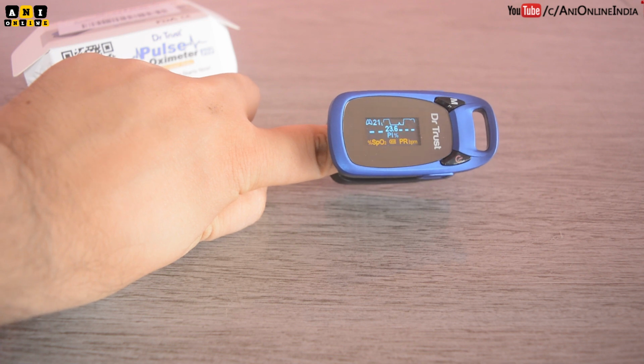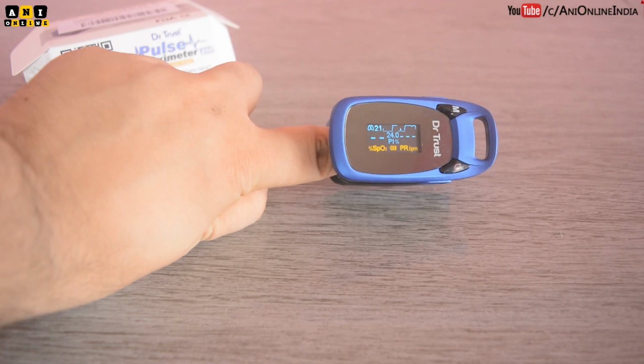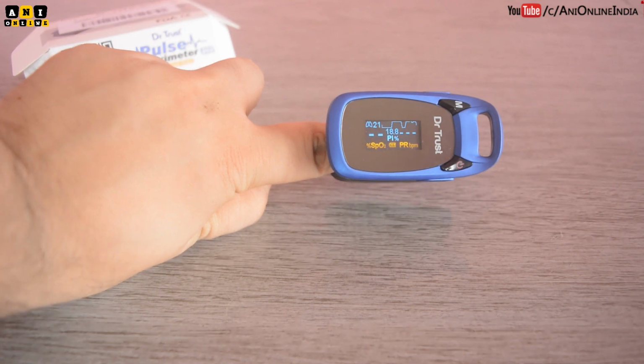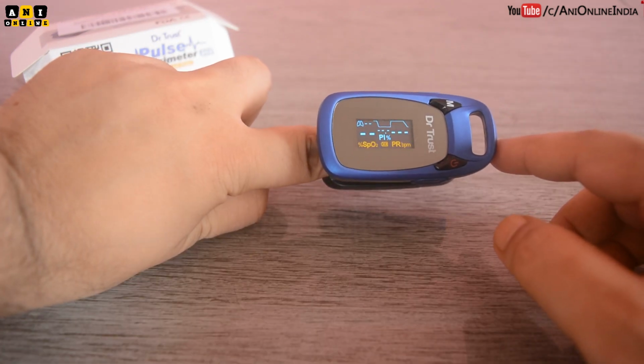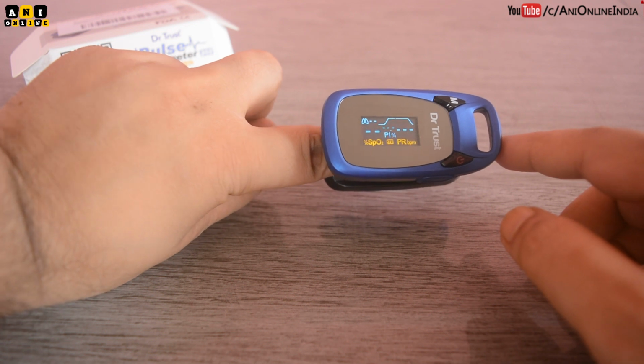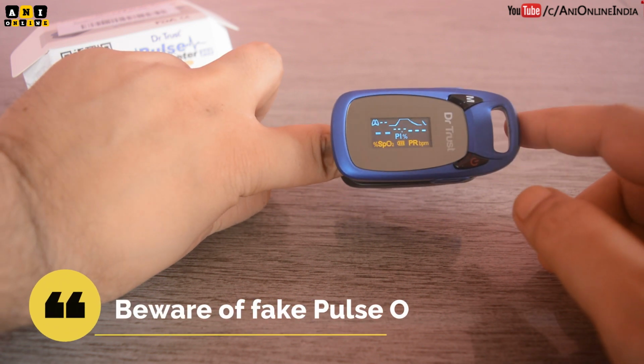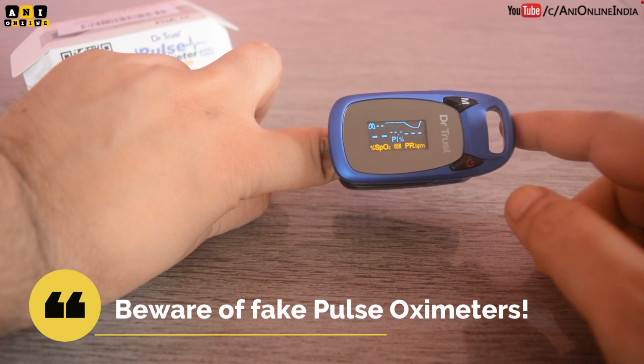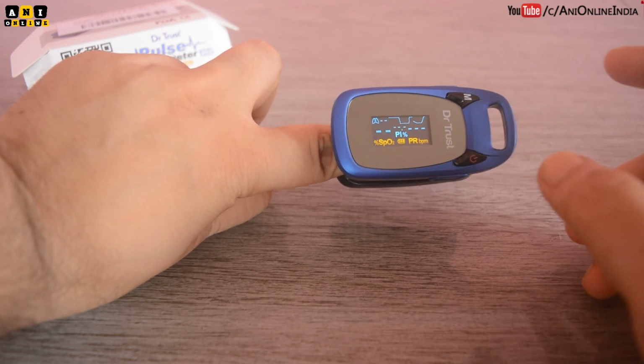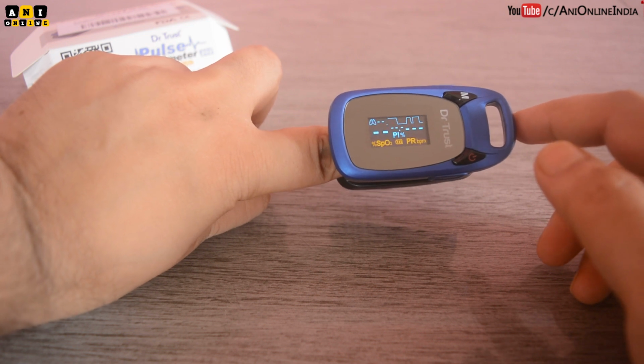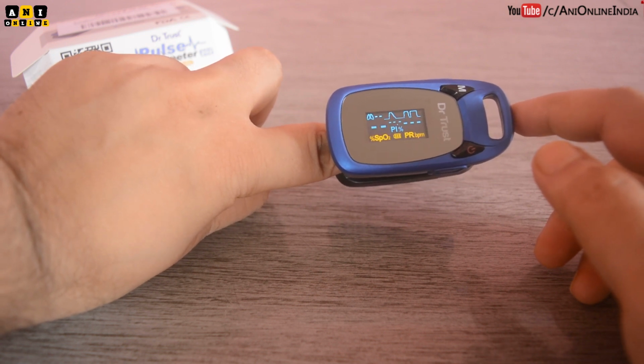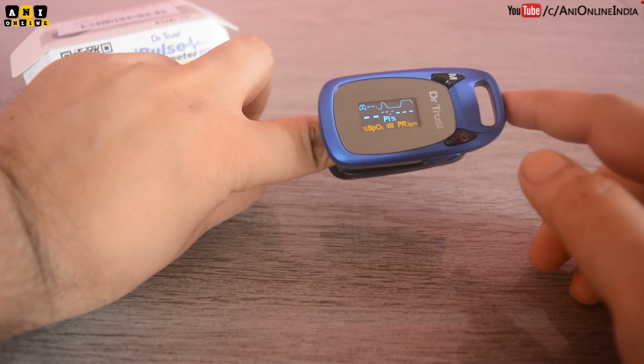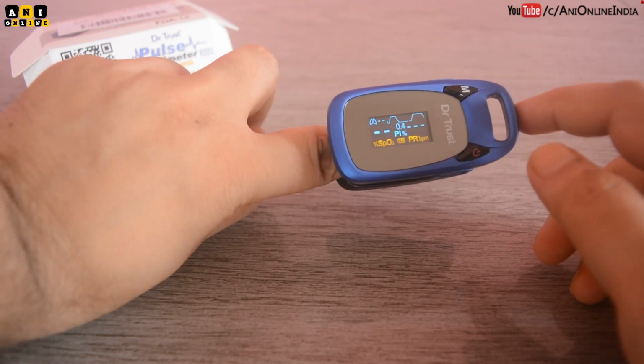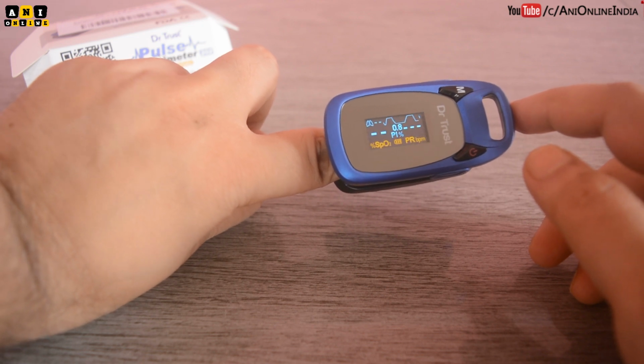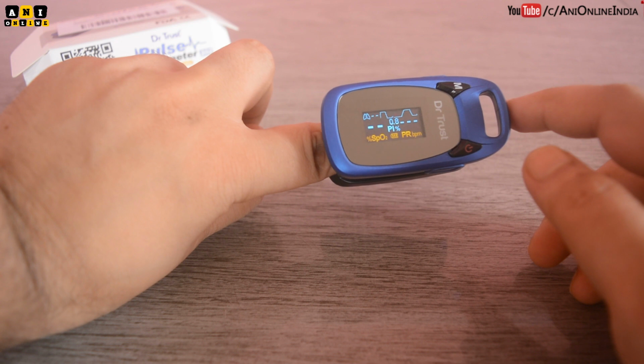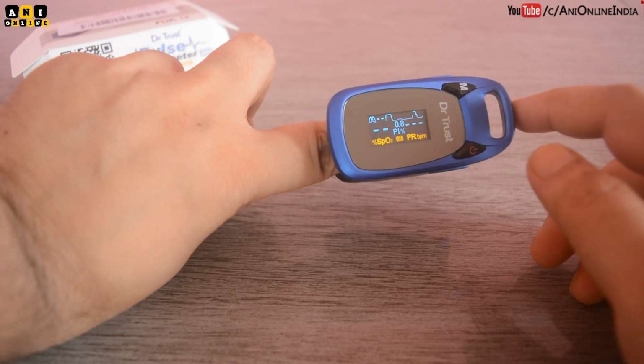And as you can see, now no reading is coming for the pulse rate and blood oxygen saturation level. From this we can say that this pulse oximeter is a genuine one and it's very accurate. But there are many pulse oximeters available in the market for a very cheap price, which show you just a random reading, and this kind of pulse oximeter generally comes from Chinese manufacturers. But this one is accurate, as you can see. So whenever you buy a new pulse oximeter, don't forget to check whether it's a genuine one or not, and as you can see, the process is really very simple.